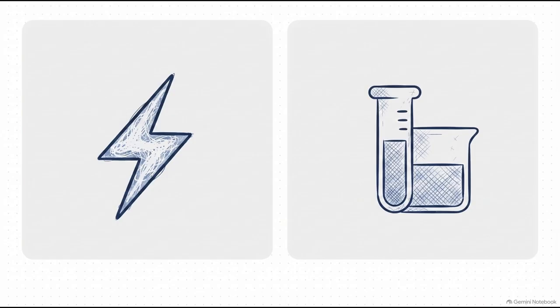And it's a fascinating contrast, really, because in a data center, water isn't just water. It's a highly engineered thermal transfer fluid. The CDU's nervous system is actually split between two totally different worlds here. On one side, it's measuring what I like to call brute force metrics, so tracking raw kilowatts of instant power consumption and primary heat removed. But right alongside that, on that exact same unit, it's tracking delicate chemistry metrics.